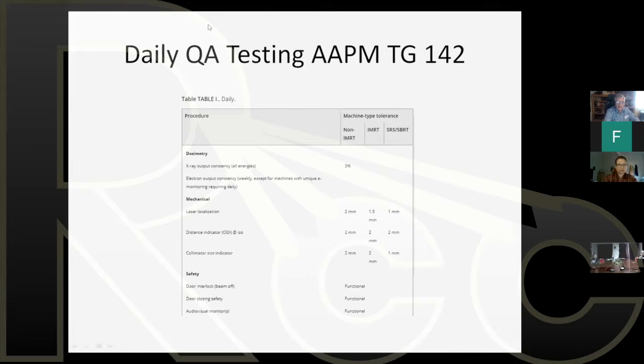The AAPM task group number 142 came out with a report which supplements the very important task group 40 report, which was really a major report addressing all aspects of quality assurance. TG40 came out before the age of IMRT, stereotactic radiosurgery, stereotactic body radiotherapy. So TG40 had to be supplemented with TG142 testing that recognized the complexity of modern machines, especially having to do with imaging and image guidance. So here is a table that shows some of the daily testing required by the Task Group 142 report.